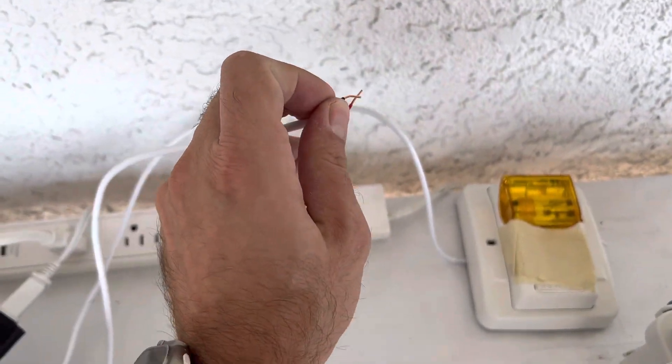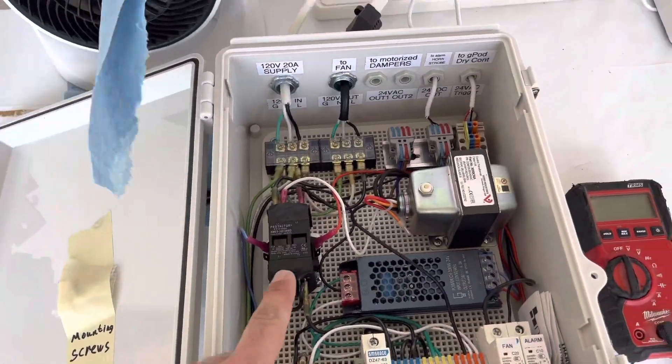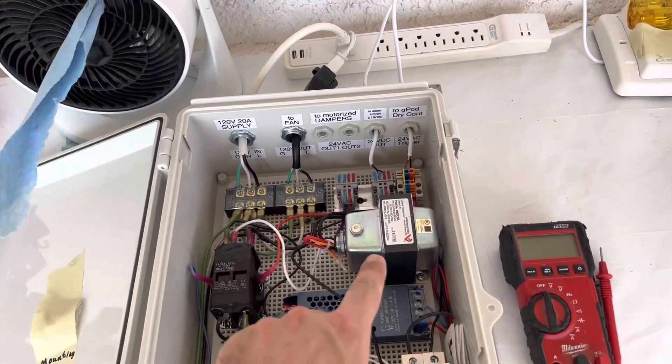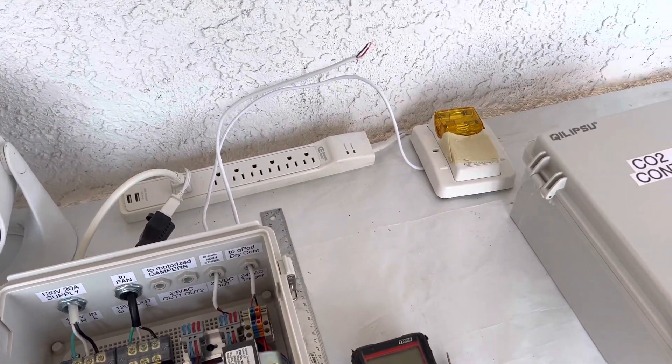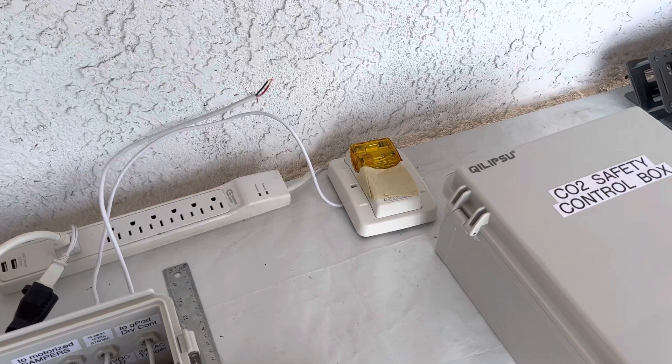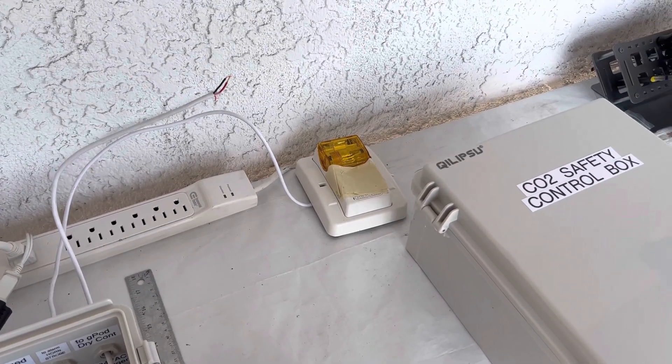When this trigger happens, the contactor closes, gives power to the fan, gives power to motorized dampers - they open - and to the alarm. This alarm is also flashing right now, but you can't see it because the video records this way.